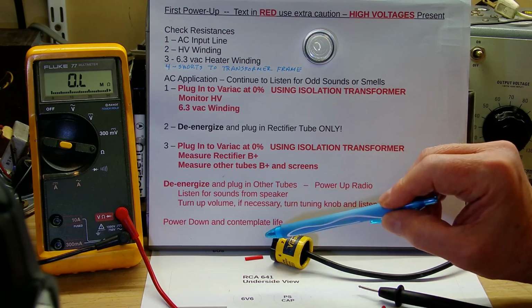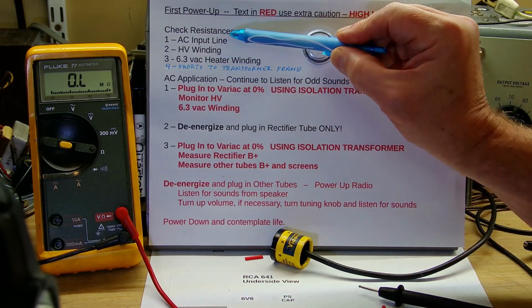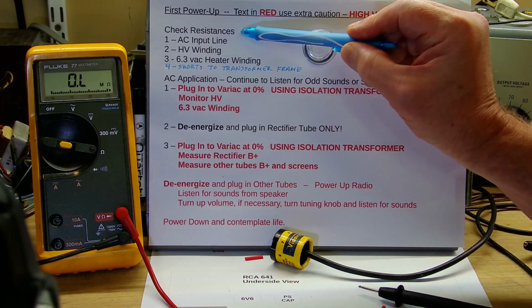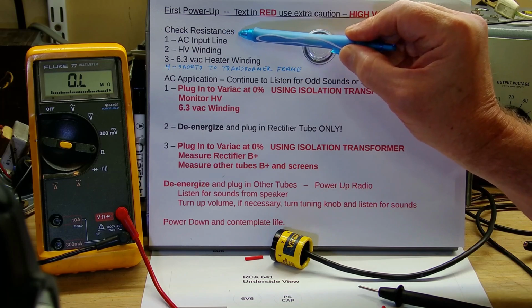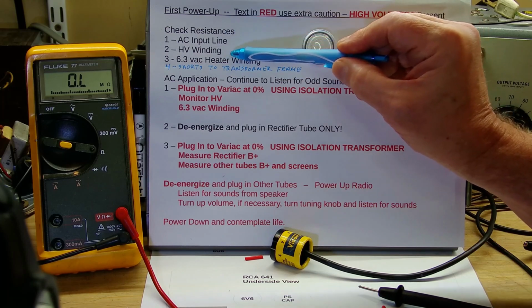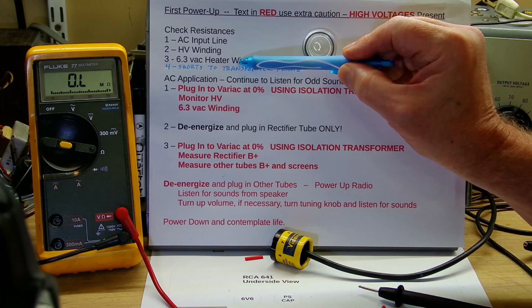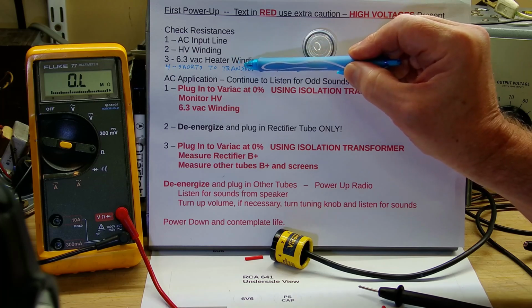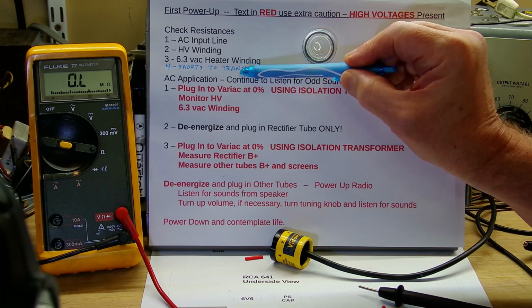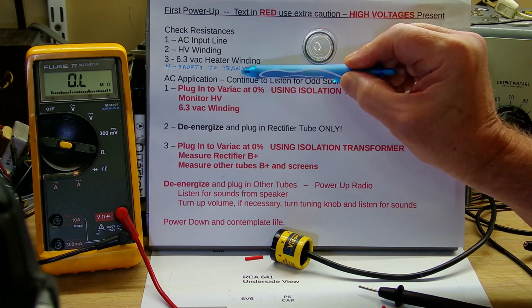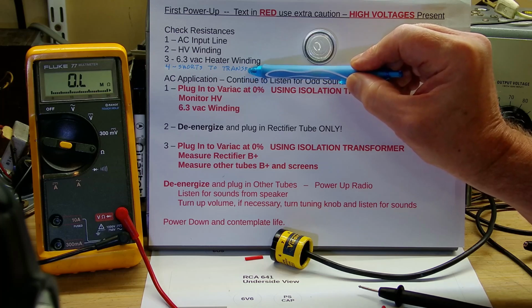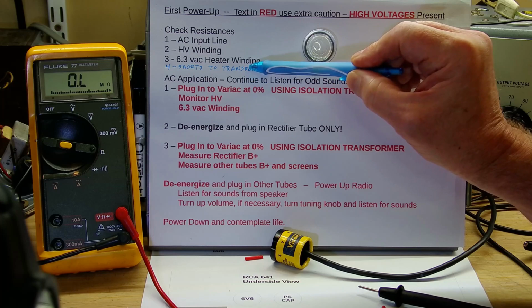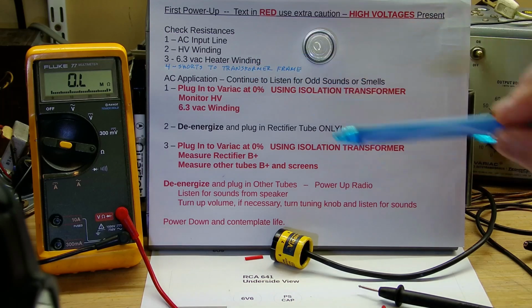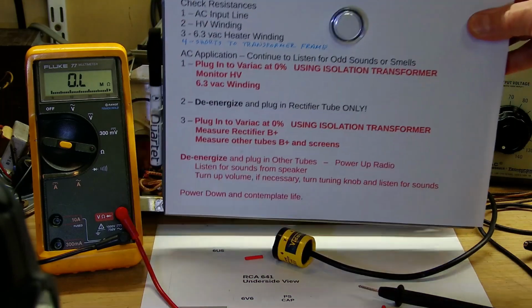The first thing we're going to do is check static resistances from the AC line and the high voltage windings, make sure there's resistance in the 6.3 volt heater winding, and then check for shorts to the casing or frame of the transformer. That would be particularly dangerous because the frame might become hot. Anyway, let's get started.